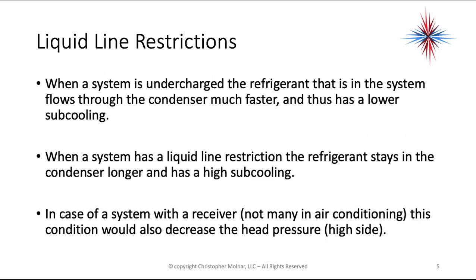When a system is undercharged, the refrigerant flows through the condenser much faster and has lower sub-cooling. When a system has a liquid line restriction, the refrigerant stays in the condenser longer and has high sub-cooling. In the case of a system with a receiver — and there are not many of these in air conditioning — this condition would also decrease the head pressure, which is the high side pressure.